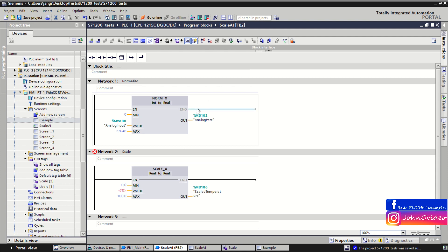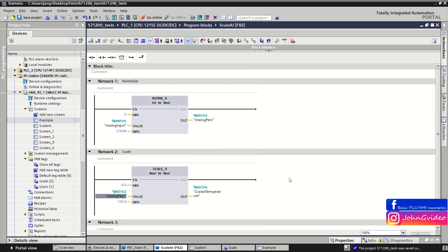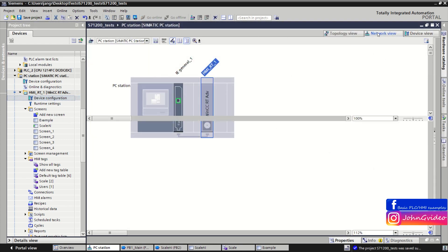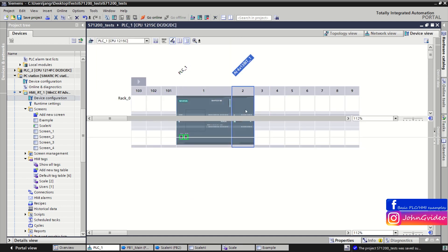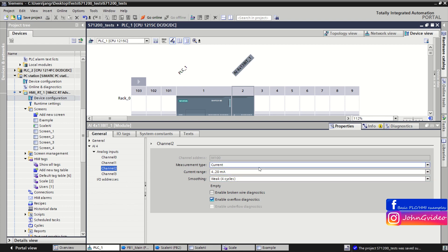On the input value we insert the value to be scaled — for this we use the output tag from the NORM_X function. So on the input we have the analog signal from the temperature sensor, which is the direct tag from the analog input card. For example on channel 2 we have an analog input signal using a current measuring range from 4mA to 20mA, with weak smoothing cycle.